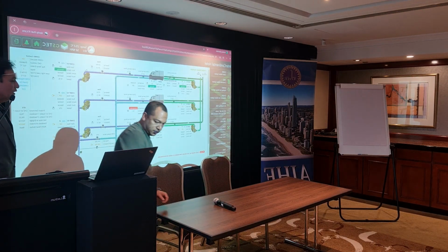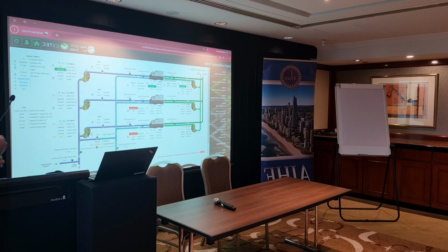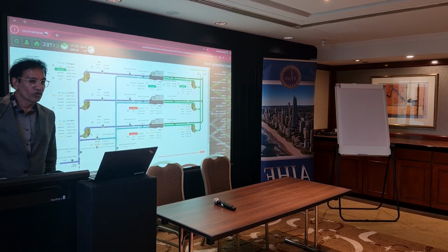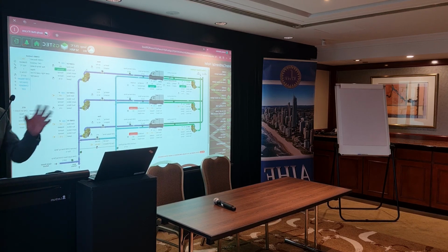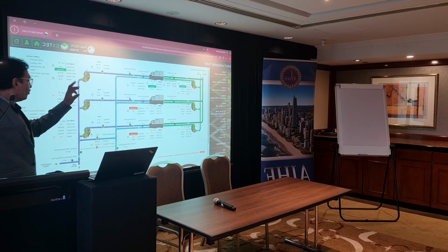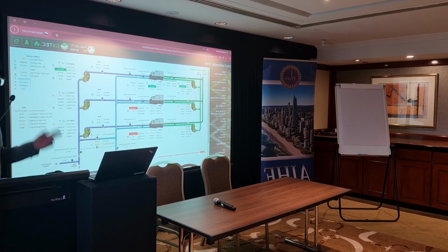No, there we are. So this is basically showing you a typical chilled water plant, and we are using some very interesting strategies. We are using variable chilled water flow based on demand, so that will cut a lot of pump energy. We also went to York, the chiller manufacturer, to see what the minimum flow rates are that you can allow across the chiller, so there'll be some interesting savings there. Also strategically looking at drifting the chilled water temperatures depending on ambient conditions, etc.